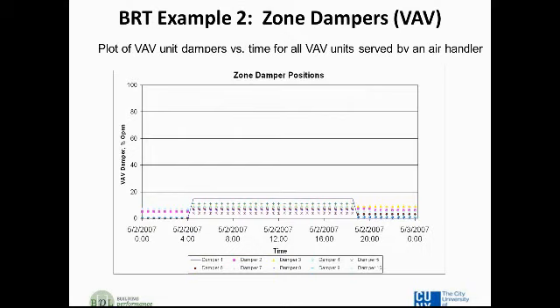Similar situation, except instead of the VAVs being starved, you can see they're all shut almost all the way down during occupied hours. In a situation like this, it seems pretty obvious that the duct static pressure is probably way too high. They're getting way too much air, and so this is an opportunity to back off on the duct static pressure. I call this the dampers or the VAVs actually being stuffed. They're not starved, they're stuffed.